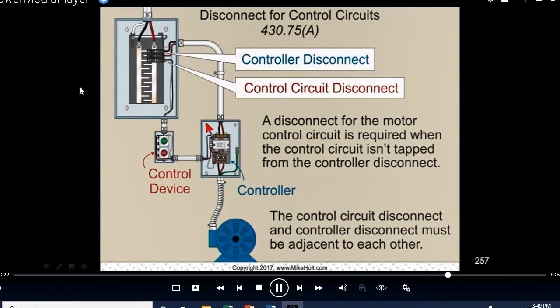So here's an example. Here's my disconnect, and it's adjacent. When I work on the controller, I need to be able to know the control circuit is off. If it's not tapped on the line side, how do I turn off my control circuit? And that's what I was telling you about that hospital. In a hospital, I had all these air handlers, and I tried to put in the control for energy management in there, and there was no information. There was no disconnect, and that's a danger there.